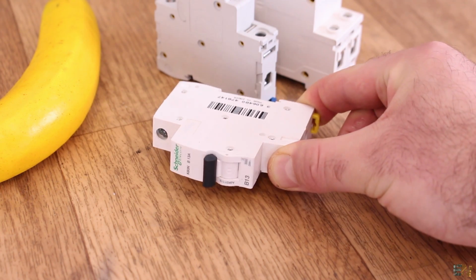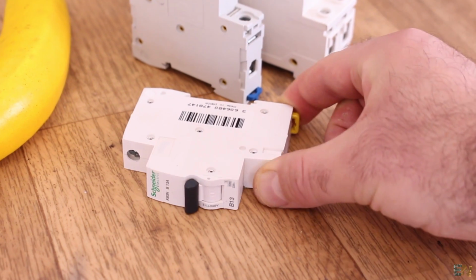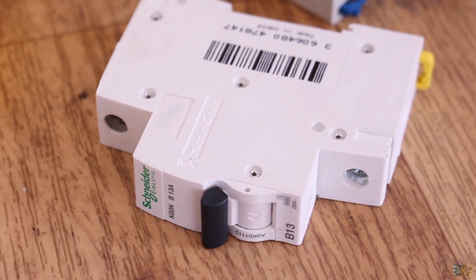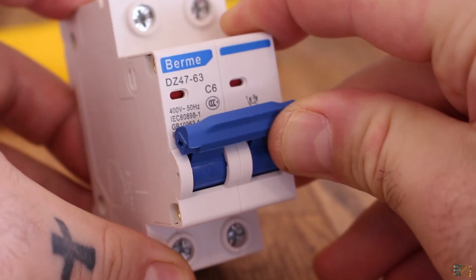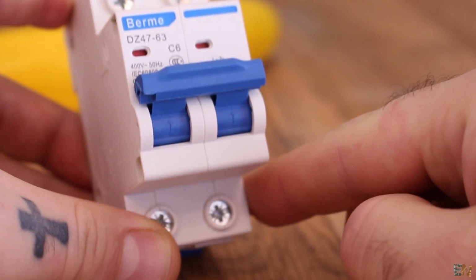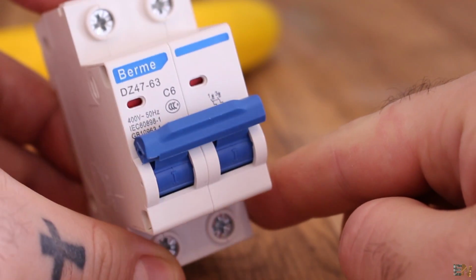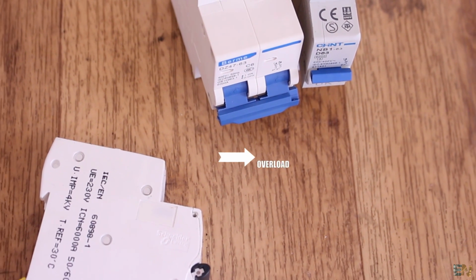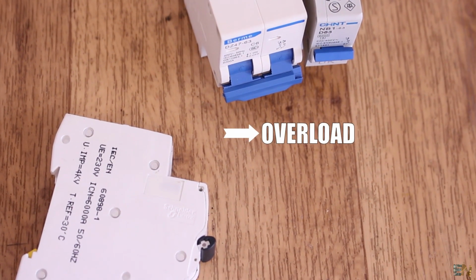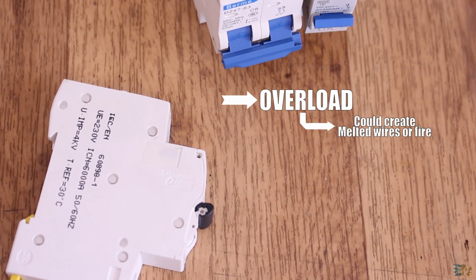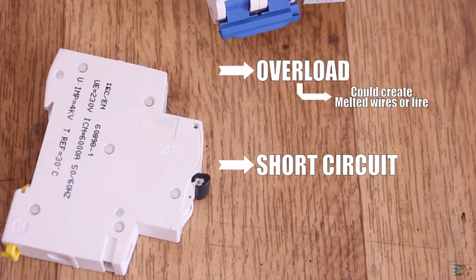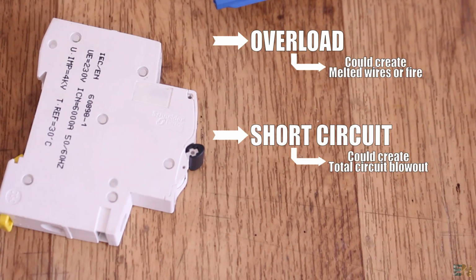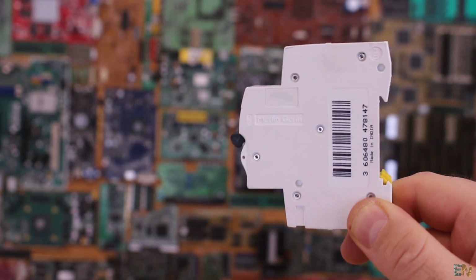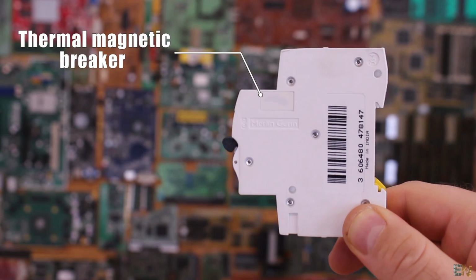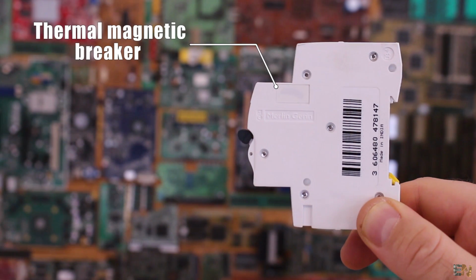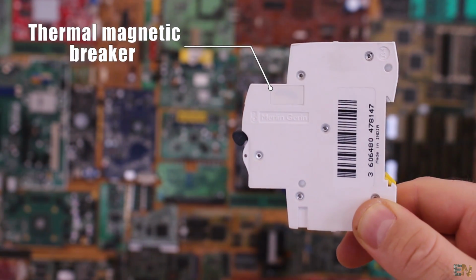What's up my friends, welcome back! So here we have the MCB, which stands for Miniature Circuit Breaker, and it could be of one pole, two poles or more. The main purpose of this device is to break the circuit in these two cases. First, when we have an overload connected during a certain amount of time. And second, when we have directly a short circuit. This is a thermal magnetic breaker, and that's because it combines both the magnetic breaker and the thermal metal dilatation breaker. So how does it do that?